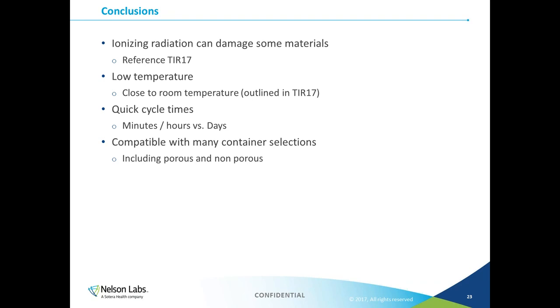Let's look at a few key takeaways for ionizing radiation. First, ionizing radiation changes materials on the molecular level, and many times these changes can adversely affect anything exposed. TIR17 is a great tool for predicting the severity of these changes ahead of time. Ionizing radiation is also a low-temperature operation, well suited for heat-sensitive products. Compared to ethylene oxide, cycle times are very low — even more so for electron beam, which only takes a couple of minutes. And ionizing radiation is compatible with a very wide selection of packaging styles and materials, both porous and non-porous.